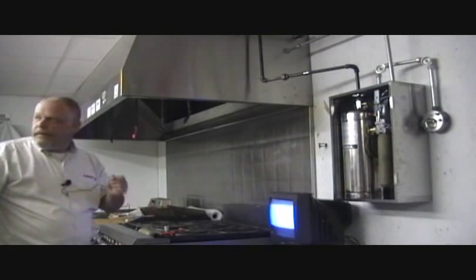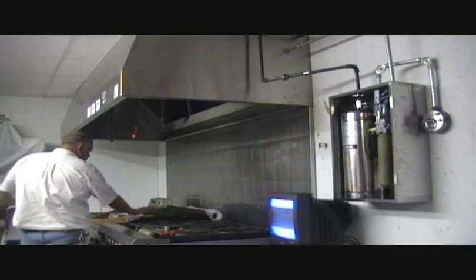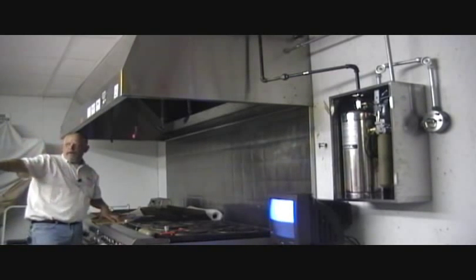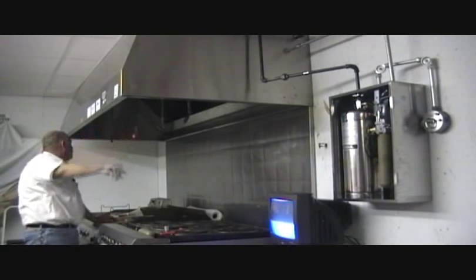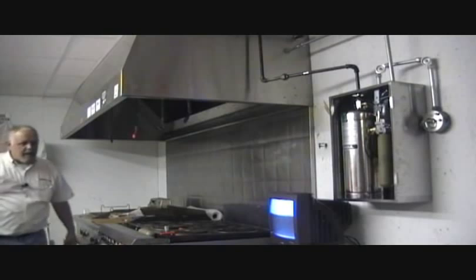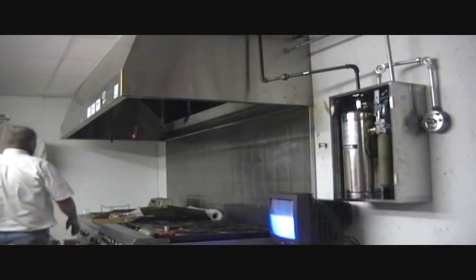if the system is failed to be serviced properly. Once again, you have a lot of grease coming off the grills and off the deep fryer. I showed you earlier how greasy that one nozzle was up in the plenum area. Now, it's all supposed to be functioning right, but yet the element burns through on the deep fryer and we have a flash fire.